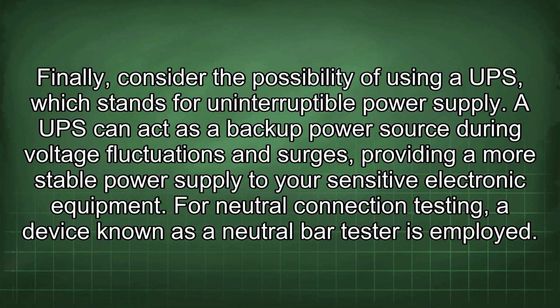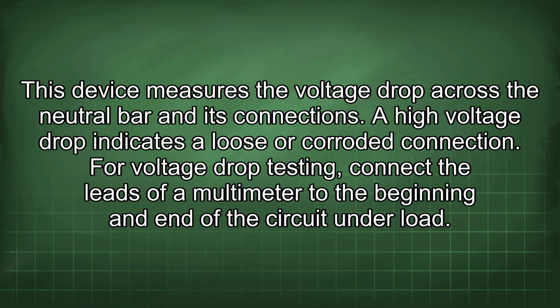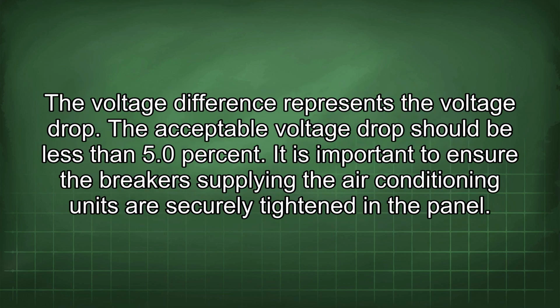For neutral connection testing, a device known as a neutral bar tester is employed. This device measures the voltage drop across the neutral bar and its connections. A high voltage drop indicates a loose or corroded connection. For voltage drop testing, connect the leads of a multimeter to the beginning and end of the circuit under load. The voltage difference represents the voltage drop. The acceptable voltage drop should be less than 5.0%.